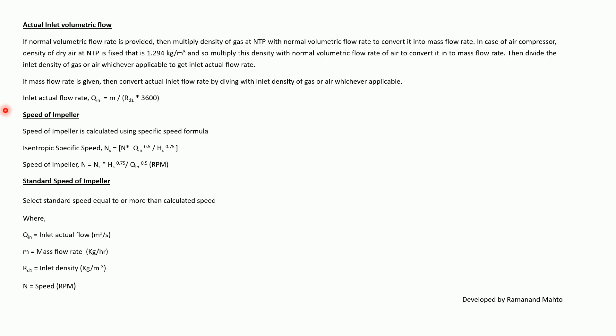The speed of the impeller is calculated using the specific speed formula. Isentropic specific speed: Ns = N × Q_in^0.5 / HS^0.75. Therefore, impeller speed N = Ns × HS^0.75 / Q_in^0.5. Select the standard speed equal to or greater than the calculated speed. Here, Q_in is actual inlet flow in m³/s, M is mass flow rate in kg/hr, Rd1 is inlet density in kg/m³, and N is in RPM.